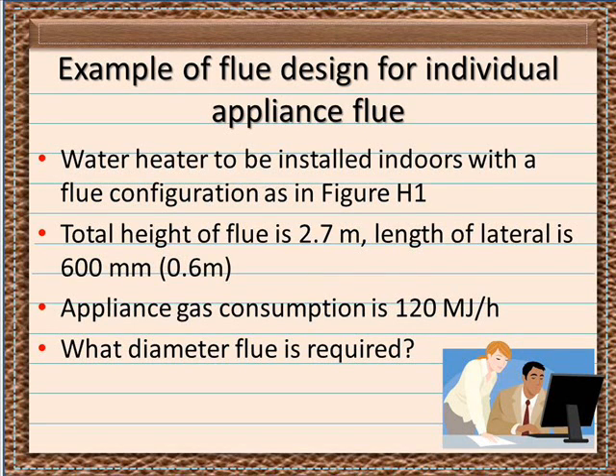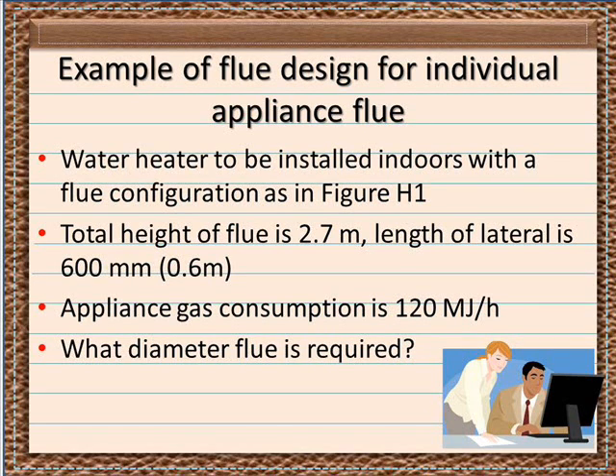Now let's consider the following example of flue design. A water heater is to be installed indoors as per Figure H1 in AS5601. The total height of the flue is 2.7 metres and the lateral length is 600 millimetres. The gas appliance consumption is 120 megajoules. What would be the diameter of the flue required for this installation?